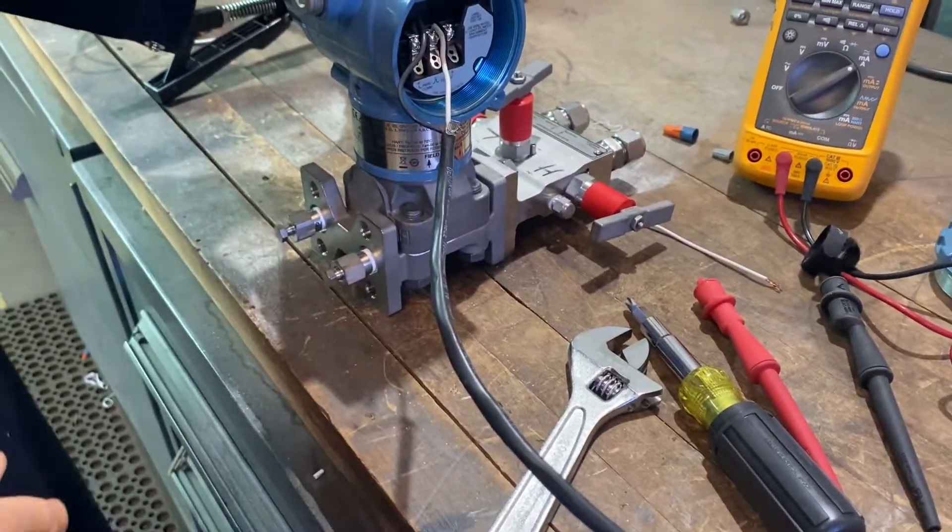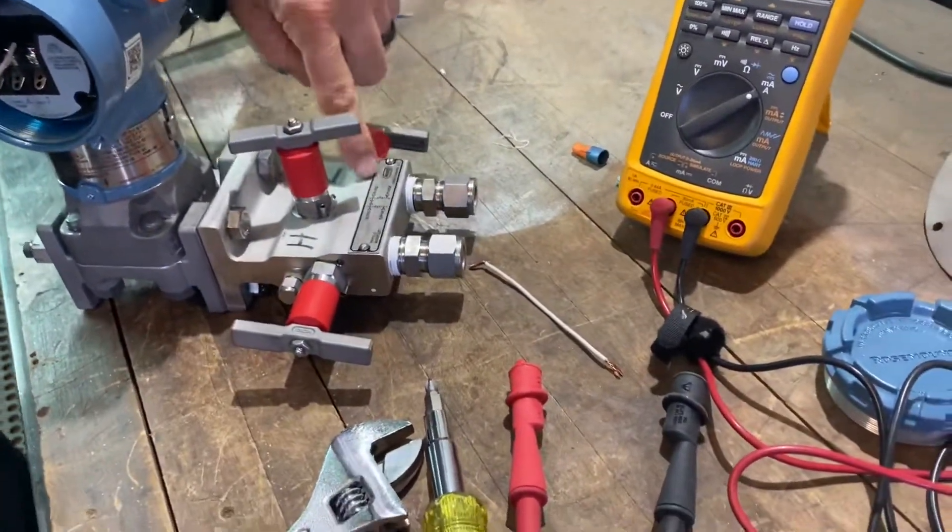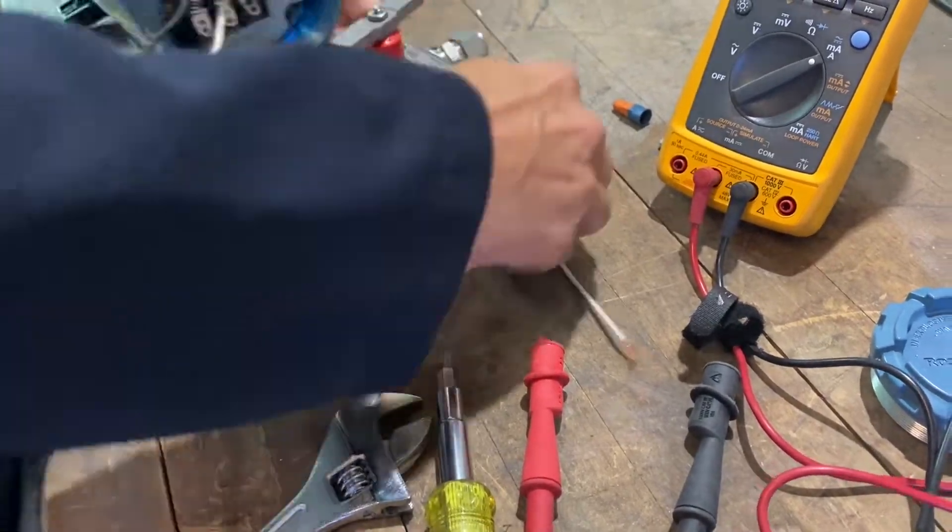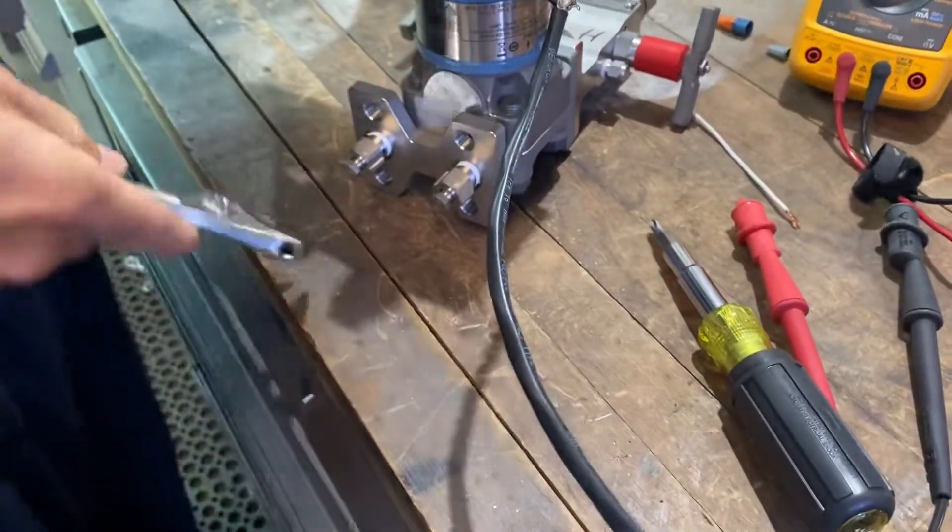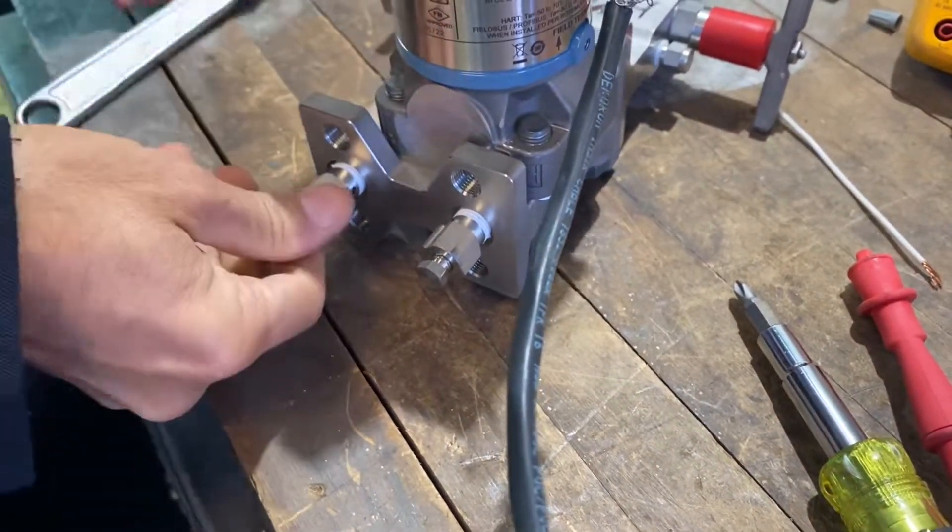but you should also check to see if your taps are plugged. And the way to do that, if you have a manifold, you can block it right here at the manifold, open up both these taps, and I would open them completely and take them out.